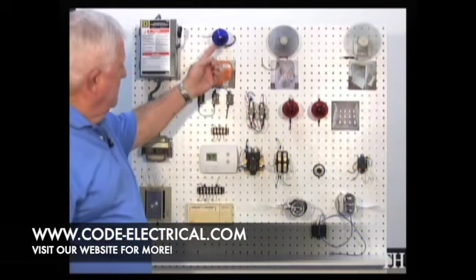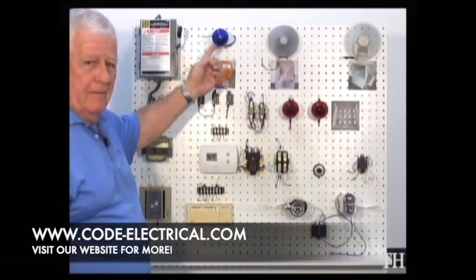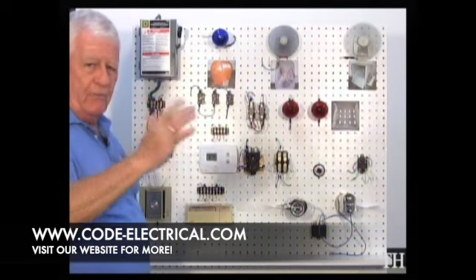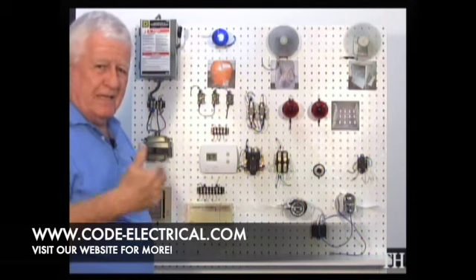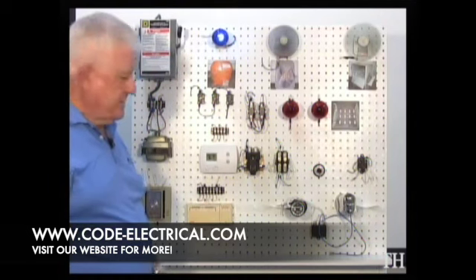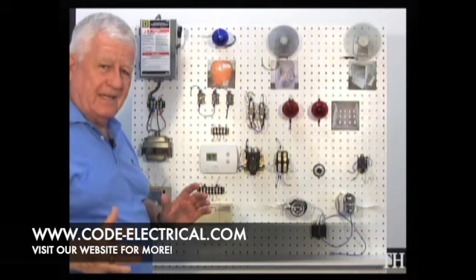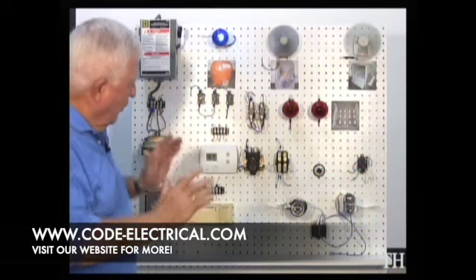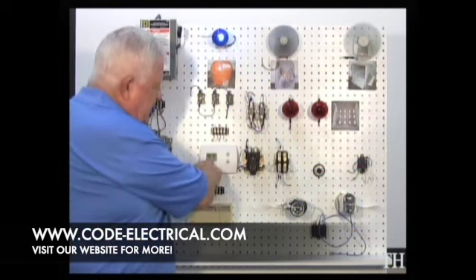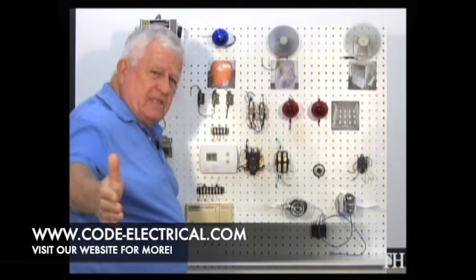Fans are on. This should start pumping. Indoor fan, outdoor fan, compressor, all three ignited. I'm making cool air coming into my house to bring us down to the setting I put it on. That's your sequence.